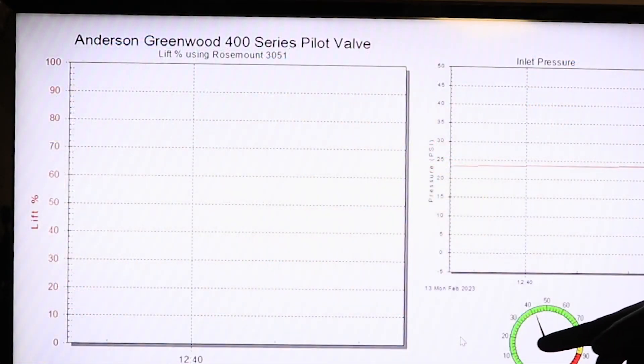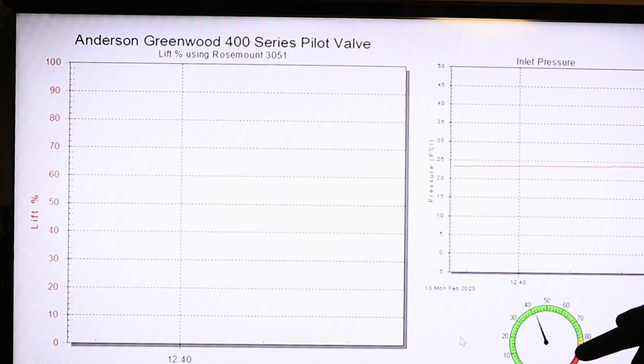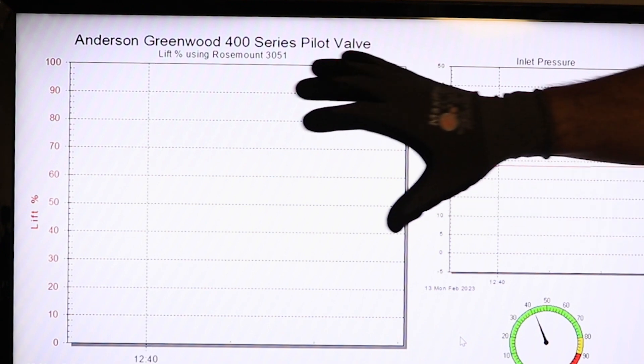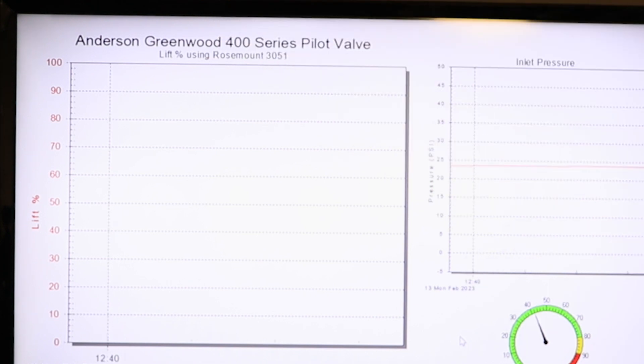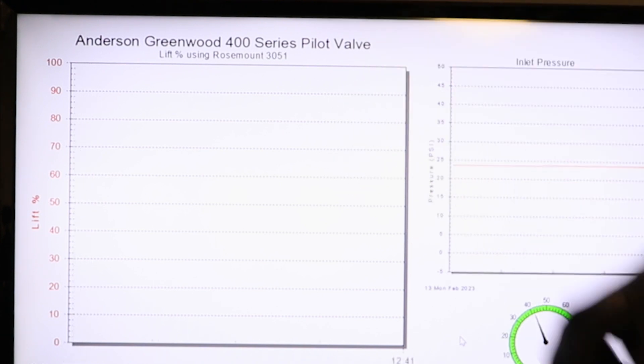In this graph, we're graphing a system pressure with a different pressure transmitter that is not part of our solution, as well as the inlet pressure. But more importantly, we're graphing the lift percent from the Rosemount 3051 that's attached to our 400 series pilot. In this graphing software, we've added the mathematical formula to convert differential pressure to lift percent.